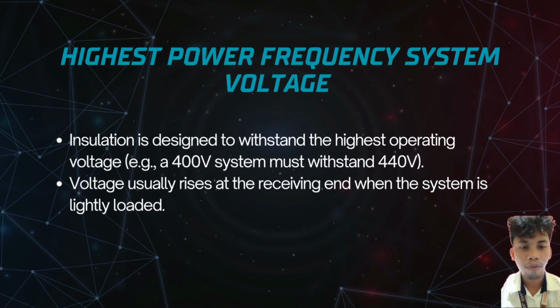What is highest power frequency system voltage? In any electrical system, there is a nominal voltage, a voltage like 400 volts. However, systems don't always stay exactly at that number. The highest voltage refers to the maximum value of operating voltage that can occur under normal operating conditions at any time at any point in the system. Insulation is designed with a safety margin.